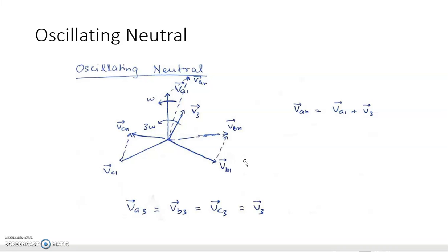The harmonics which are triplen, that is multiples of 3, you will often hear this word triplen, behave in a similar manner as they are co-phasal, or in phase, with their respective phases. The non-triplen harmonics, which are not the third order harmonics, behave in a similar manner to the fundamental and have 120 degree phase displacement between them. So that is not a part of concern for us.